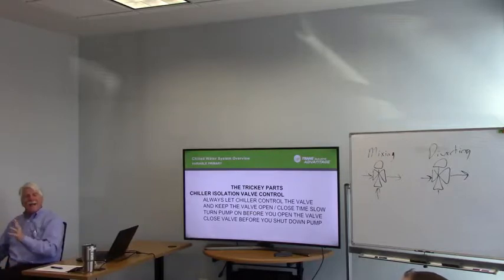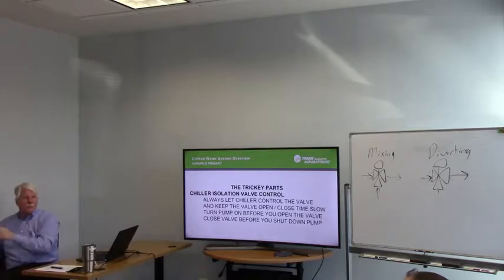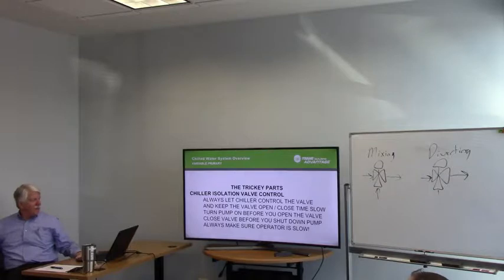We got lots of head available at that valve. That pump's working hard. So as soon as we start cracking the valve, we're going to have good flow everywhere. So that's why you want to get the pump going first. And again, make sure the operator is slow.